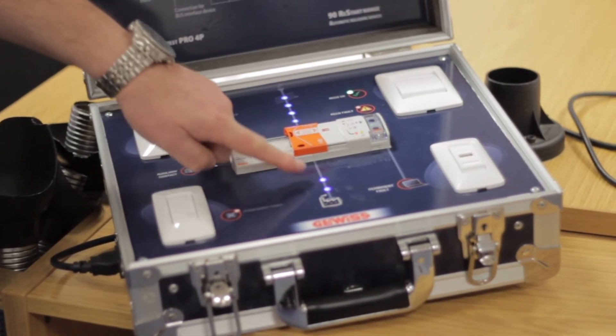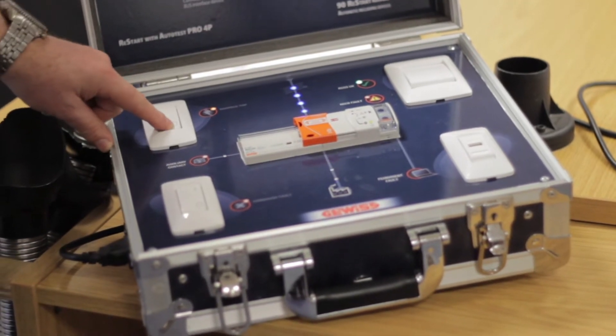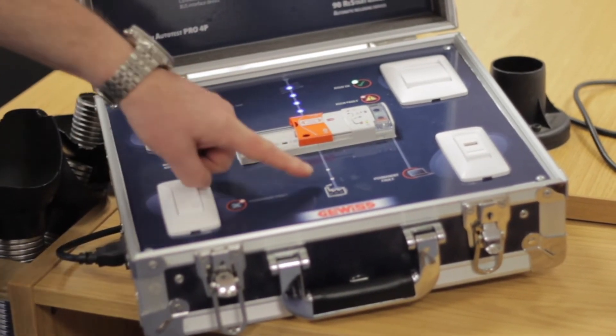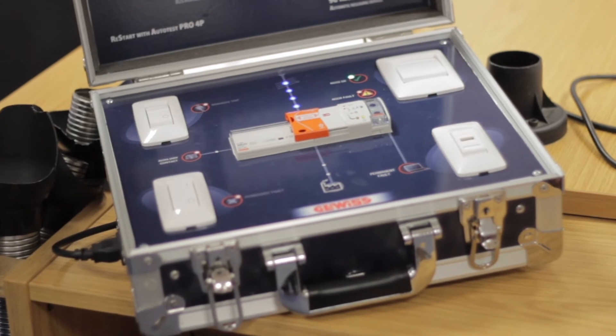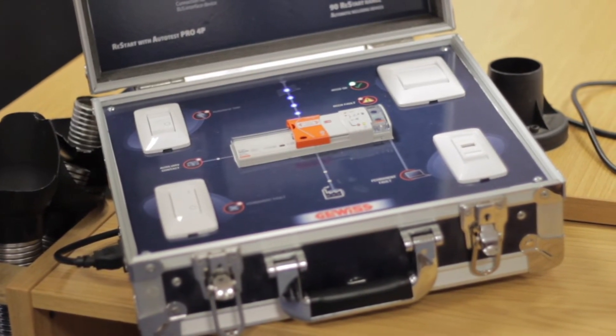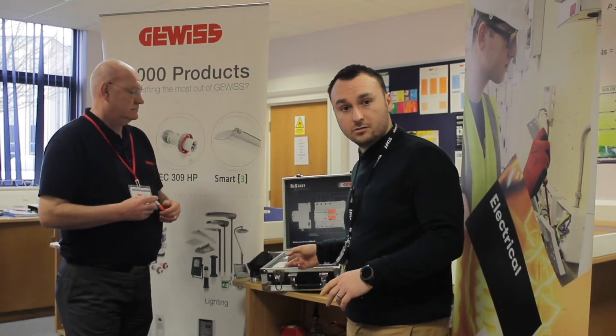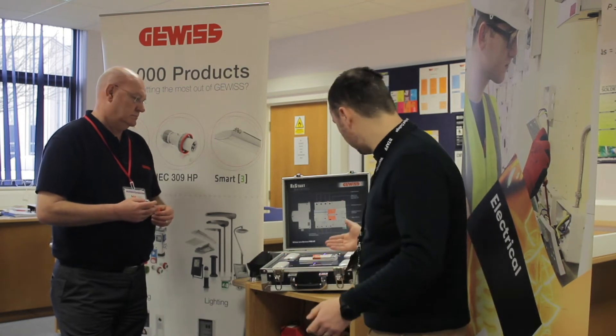It shuts down momentarily, but notice there's no loss of power. It has tested itself, wiped its contacts, done its maintenance, and come back online with no loss of power. That's the auto-test part, and that is the part that is actually patented by Gewiss. The obvious benefit is that there's no downtime — less downtime for factories, and no need to plan it into your maintenance schedule.